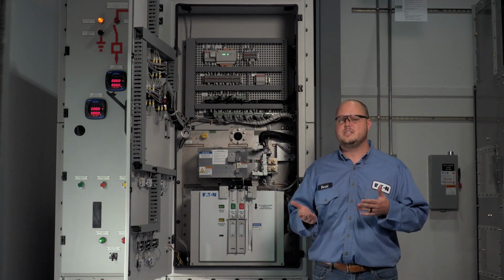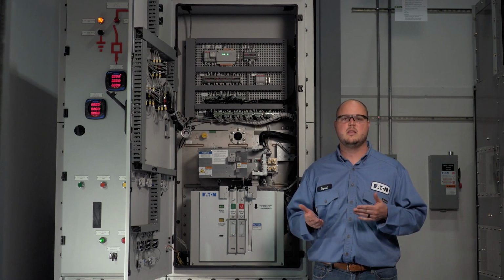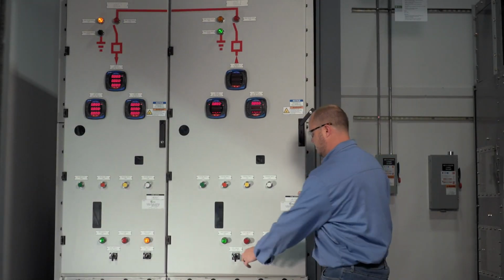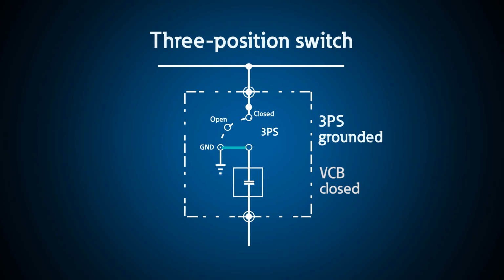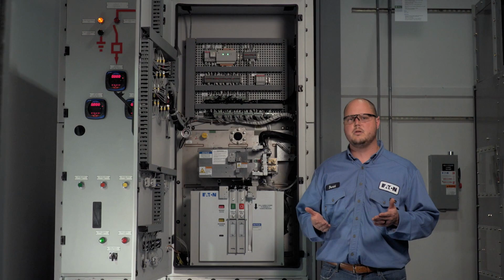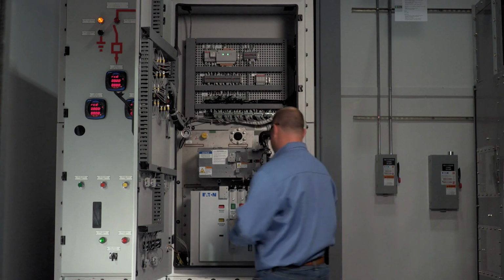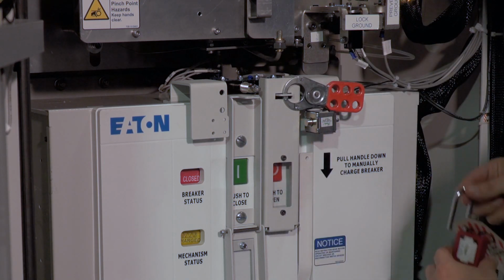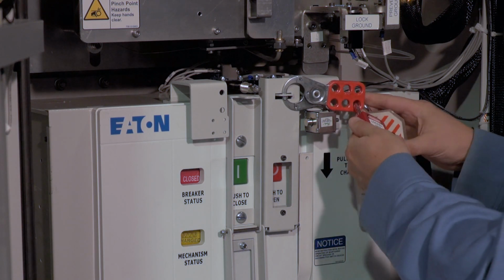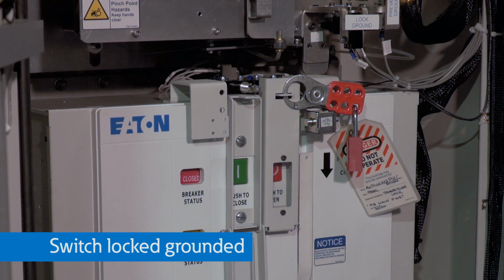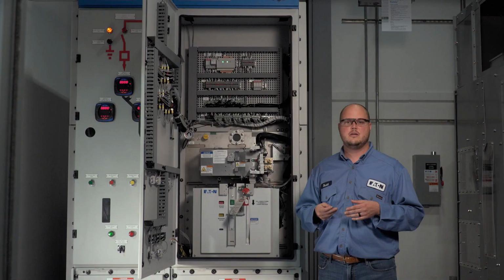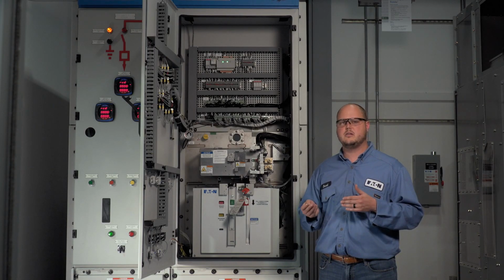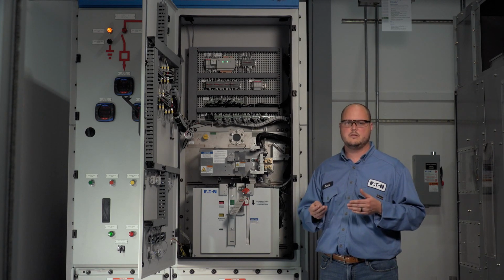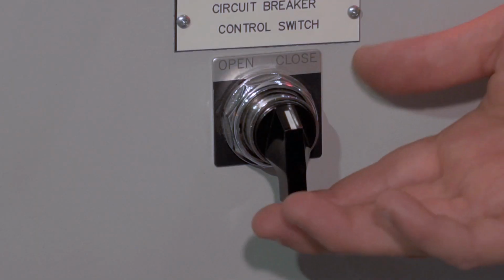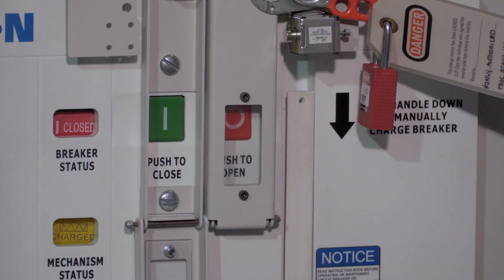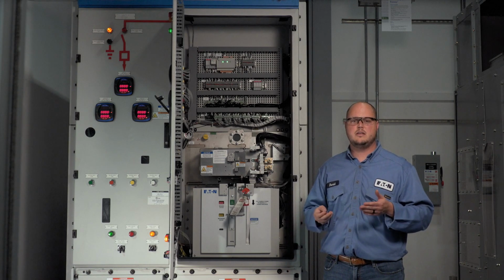Now that the operator has verified that the switch is grounded, the breaker must be closed before the breaker open push button interlock cover can be applied. After closing the breaker, which grounds the breaker cables through the 3-position switch, the breaker open push button interlock cover can be closed and locked in place. Notice there is a limit switch behind the cover that engages when the lock cover is closed. The switch disconnects the trip circuit and prevents opening of the circuit breaker electronically, while the button cover prevents mechanically opening the circuit breaker. The circuit breaker and circuit breaker cables are now locked in the grounded position.